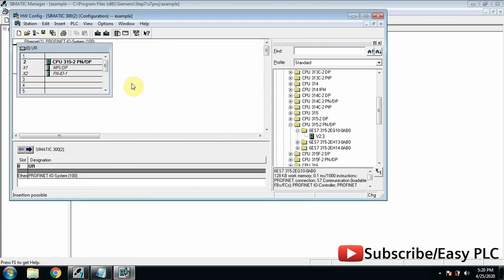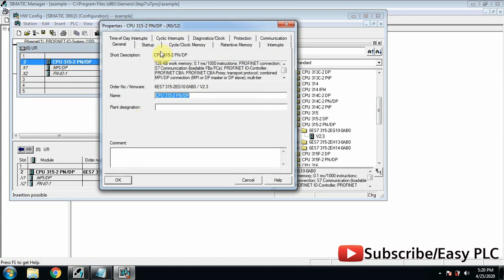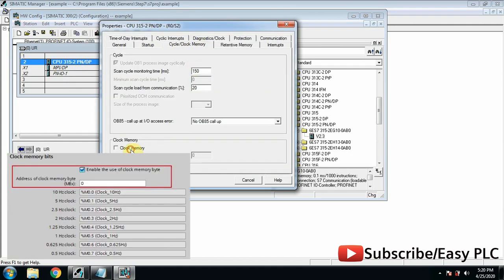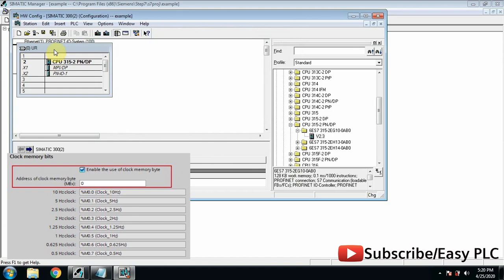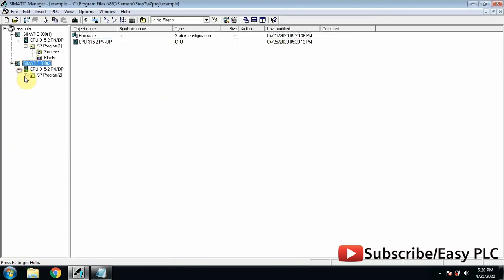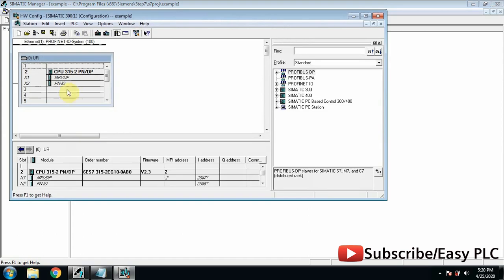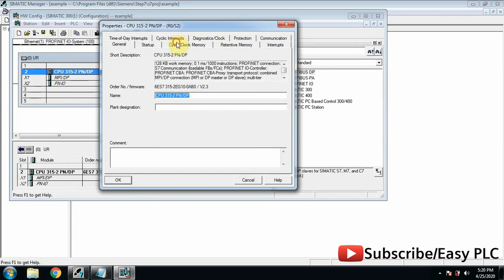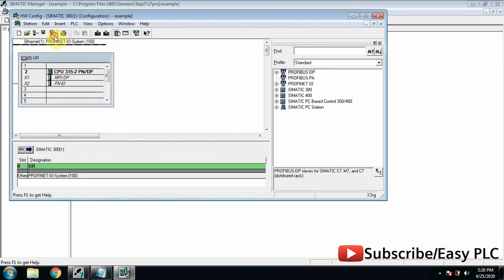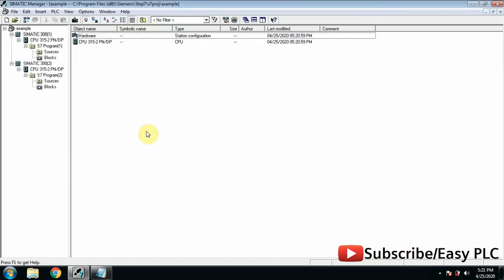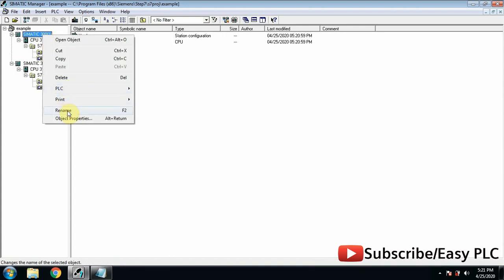We will change the IP address because local and remote PLC stations should have different IP addresses. From PLC settings we will enable the clock memory byte and click OK. You can see what the clock memory byte is from the table on the left. Now we will also enable the clock memory byte in the local PLC. We can rename the PLC as local and remote so that it will be easy to understand the programming.